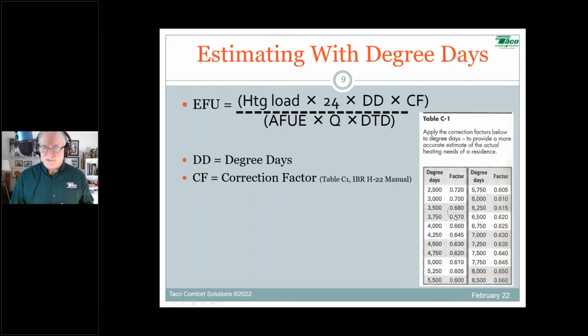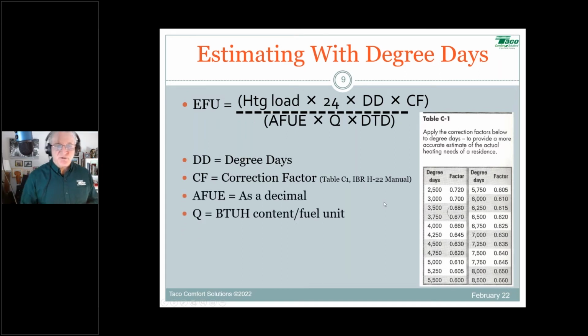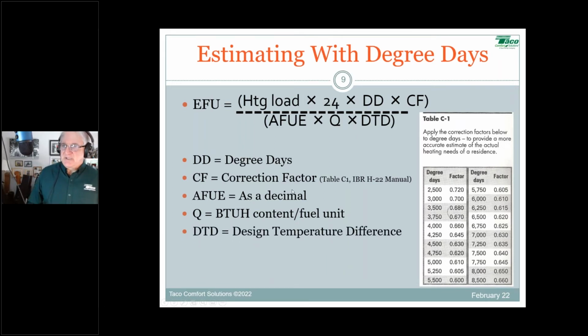There's your correction factor table right there for CF. That's your correction factor. Again, that's in your downloads. AFUE stated as a decimal. Q is the BTU content of the fuel per unit. So again, that's 138,500 BTUs per gallon of number 2 fuel oil, 100,000 BTUs per therm of gas, etc. So that's what Q is. And then DTD is your design temperature difference. In our example, we had 70 degrees indoors, minus 12 outdoors. That's a design temperature difference of 82 degrees, okay?